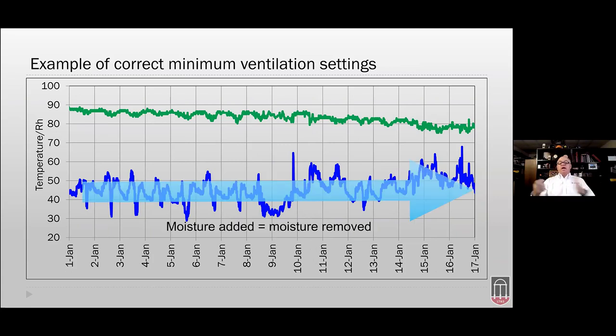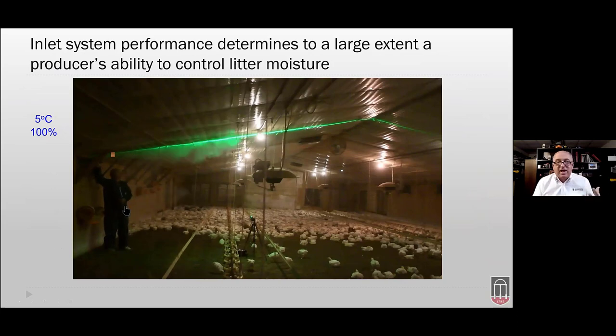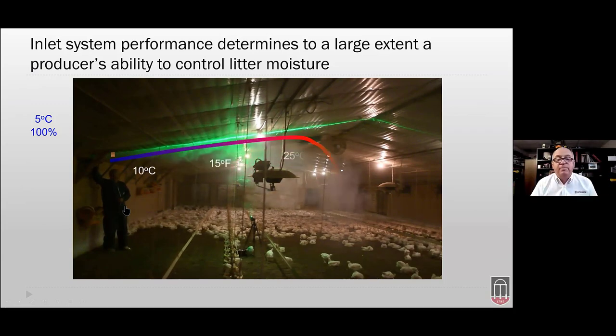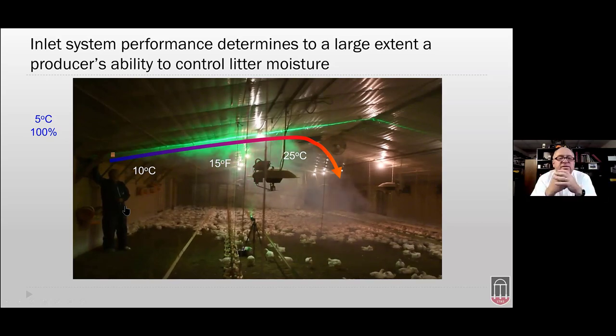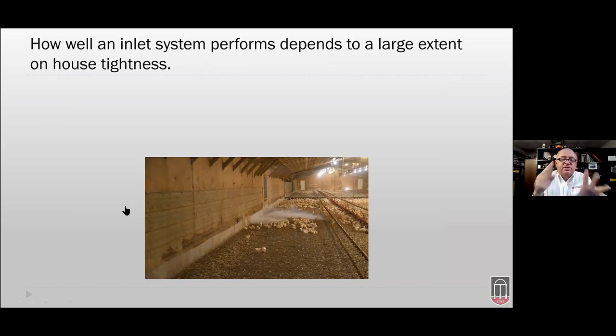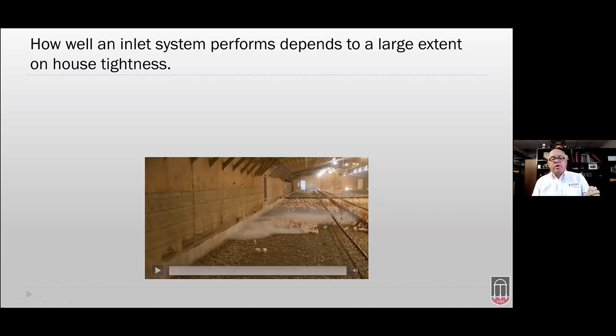When we look at factors affecting accuracy — house tightness, stratification, inlet performance, air movement — all are related to ventilation. The app gives an estimate, but how accurate our moisture control is depends largely on how well our inlet system is working. The better the system, the more we can dry incoming air and pull moisture from litter. How well an inlet system works depends greatly on house tightness: if all air enters through floor cracks rather than inlets, it will not dry litter. It's the quality of air brought in as much as the quantity.